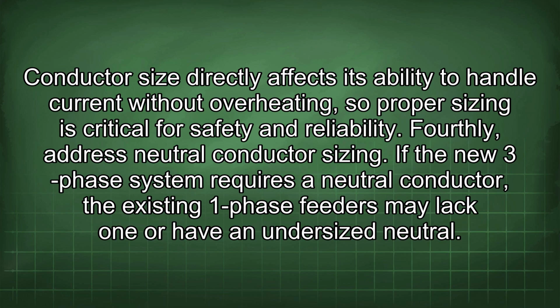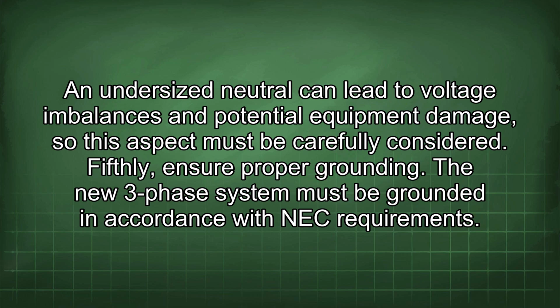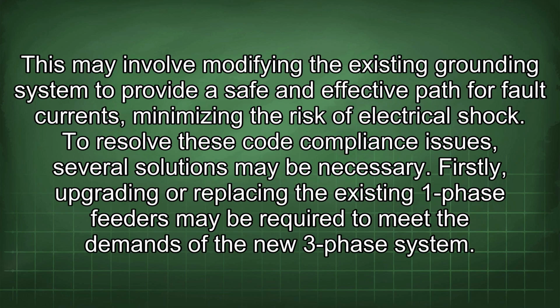Fourthly, address neutral conductor sizing. If the new three-phase system requires a neutral conductor, the existing one-phase feeders may lack one or have an undersized neutral. An undersized neutral can lead to voltage imbalances and potential equipment damage, so this aspect must be carefully considered. Fifthly, ensure proper grounding. The new three-phase system must be grounded in accordance with NEC requirements. This may involve modifying the existing grounding system to provide a safe and effective path for fault currents, minimizing the risk of electrical shock. To resolve these code compliance issues, several solutions may be necessary.